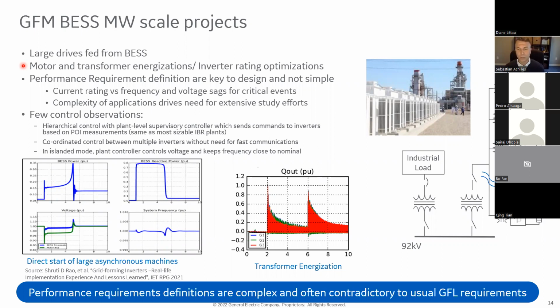Transformer energization was also a consideration. Some of the transformers were energized together with the batteries, like a soft start of the transformer to avoid their inrush currents. But in some cases, we had to look at energization of transformers like a standard energization, and dealing with the inrush of the transformer, as you can imagine, is a challenging activity from an inverter. So that was part of the design considerations.